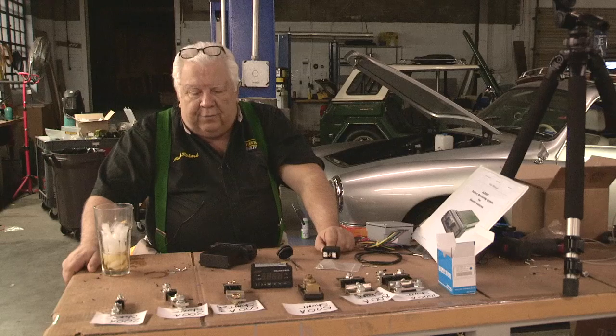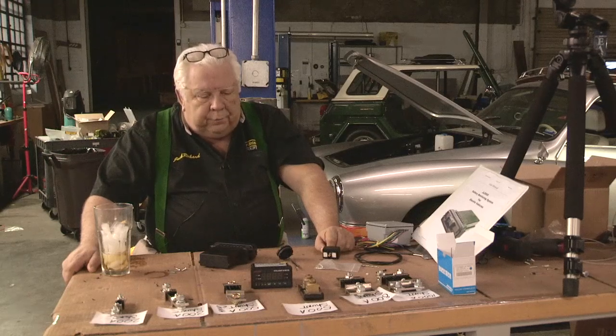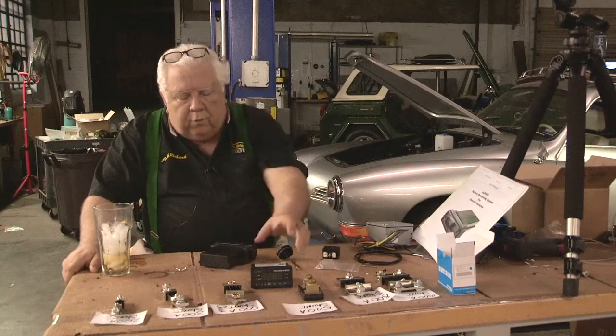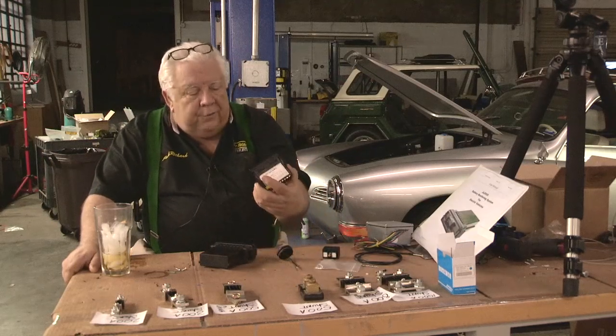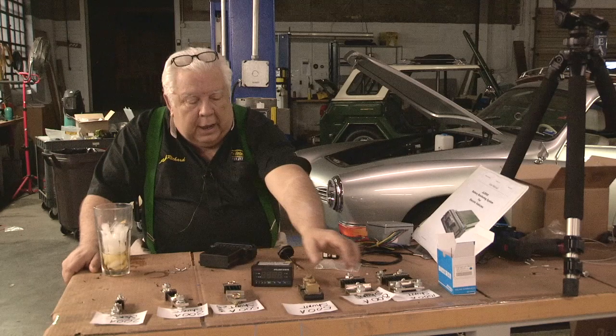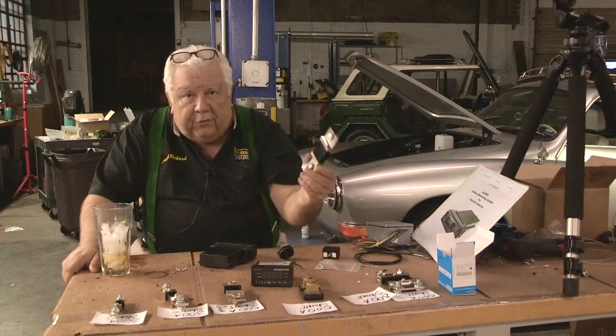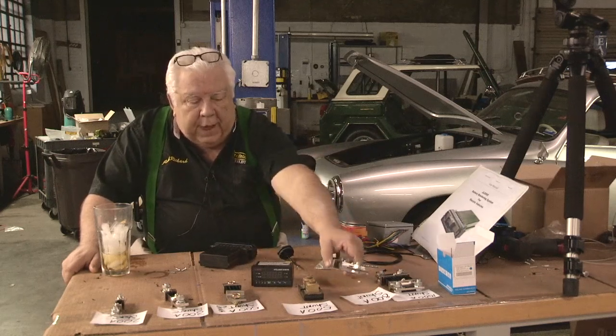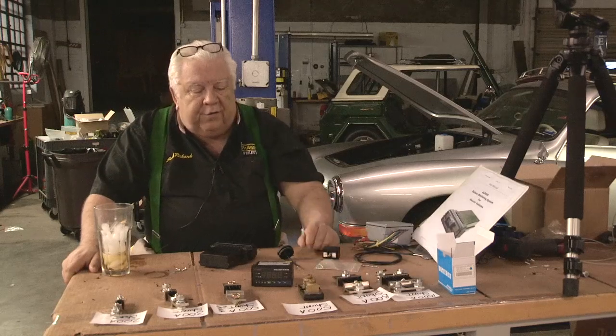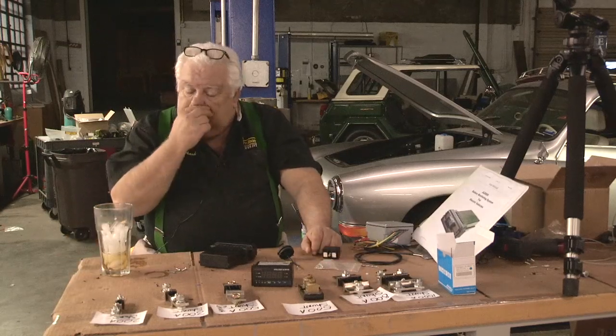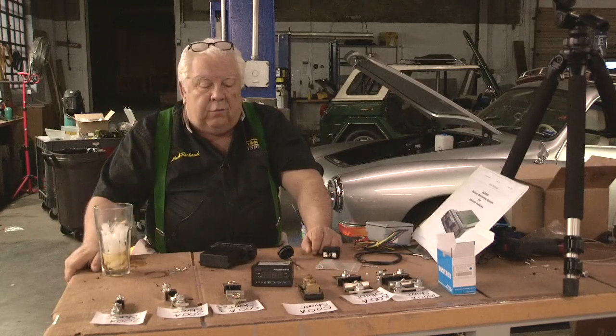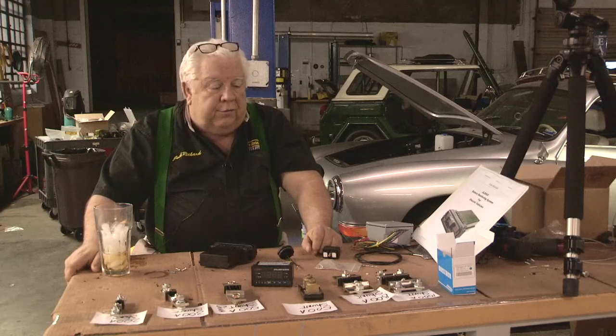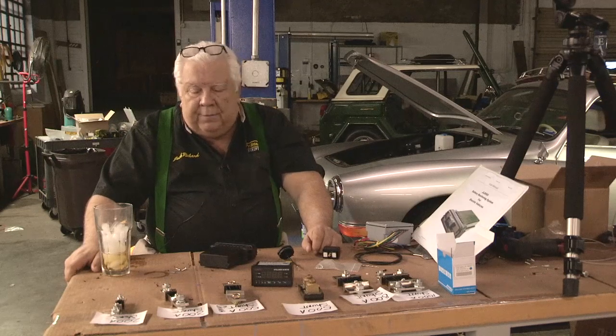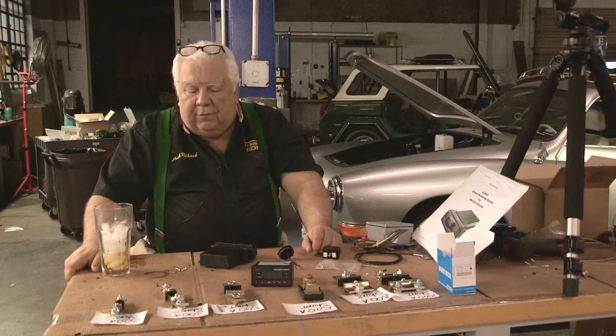Shunts can be expensive. The JLD505 is Chinese, and it assumes, like these Chinese shunts, that they're 75 millivolts. You can't change that. But you can change the size. So you can change it to 75 millivolts at 500 amps. You can change it to 75 millivolts at 1000 amps. It always stays 75 millivolts.